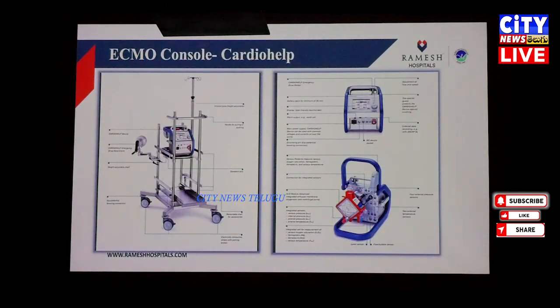This is the other advanced version by Maquet called the Cardiohelp. Now here, in the previous one, the oxygenator and the pump are two separate units. Here it is incorporated into one system. So this is a combination of a pump as well as the oxygenator. And this is how the system looks. This is called the Cardiohelp system by Maquet.